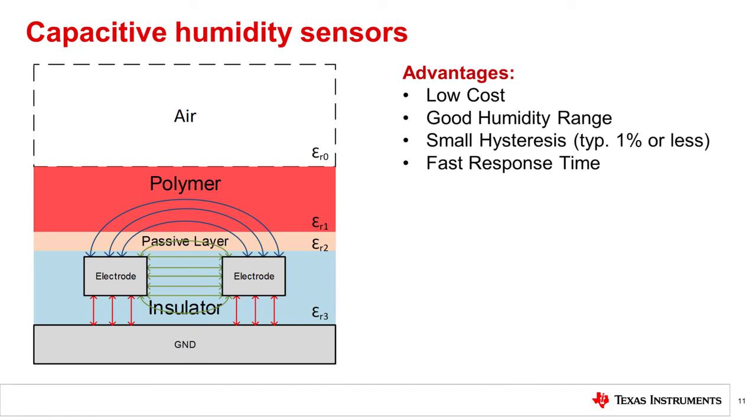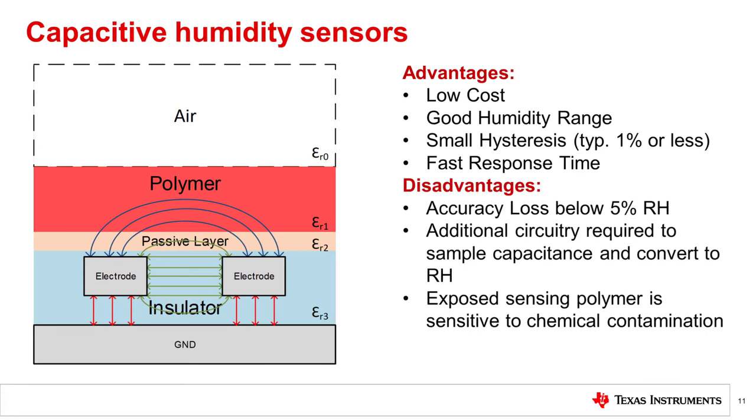In general, capacitive sensors are similarly low in cost to resistive humidity sensors. They have good functional humidity range from 0 to 100% and very small hysteresis, typically 1% or below. They also provide a very fast response time to steep changes in humidity. Among the drawbacks of these sensors is that they typically have poor accuracy below 5% RH and require additional complex circuitry and characterization to sample capacitance and convert it back to relative humidity. Additionally, due to the opening of the top of the package, these sensor types are sensitive to exposure to chemicals and require special consideration in manufacturing.